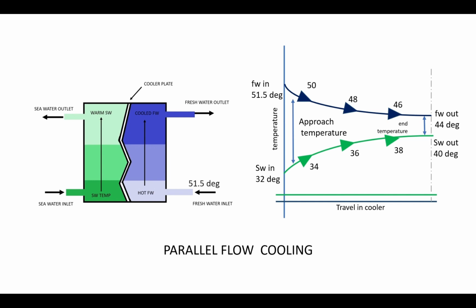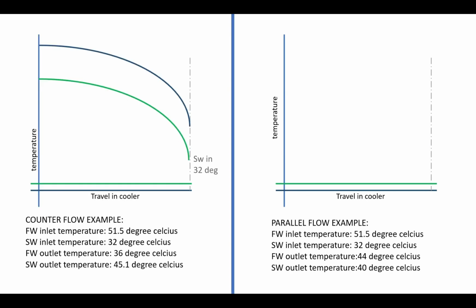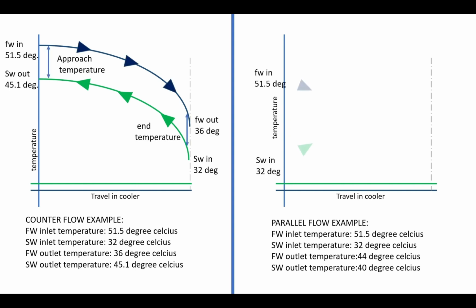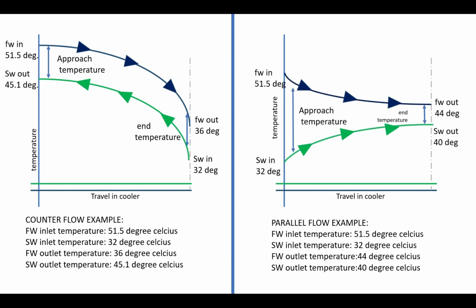Fresh water enters the system at a temperature of 51.5 degrees and will leave the system at a temperature of 44 degrees Celsius, while seawater enters the system at a temperature of 32 degrees and leaves at 40 degrees Celsius. The fresh water outlet temperature is higher than the seawater outlet temperature. The counterflow cooling system generates much more heat transfer than the parallel flow cooling system because the fresh water outlet temperature with counterflow cooling is less than the seawater outlet temperature, and the difference between inlet and outlet temperature of fresh water is greater.